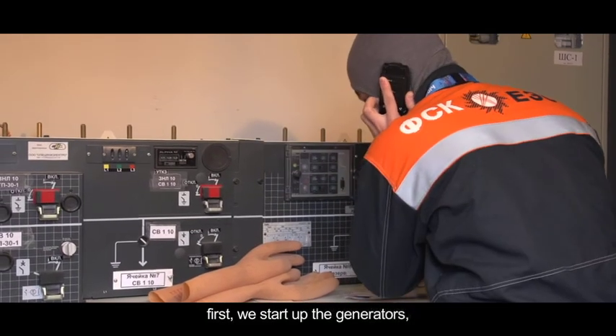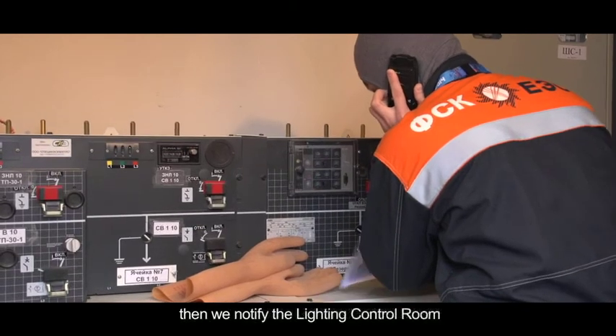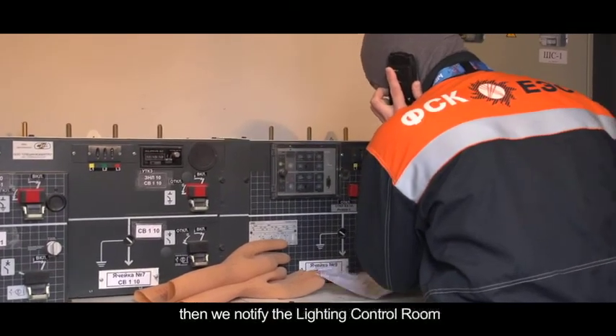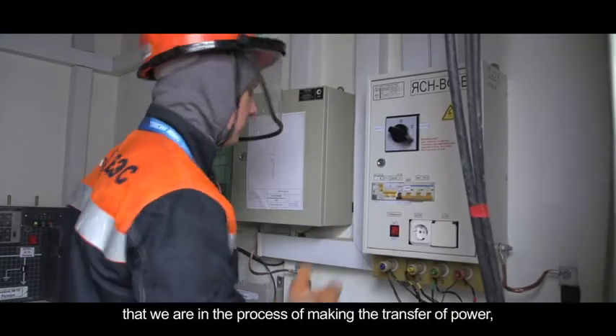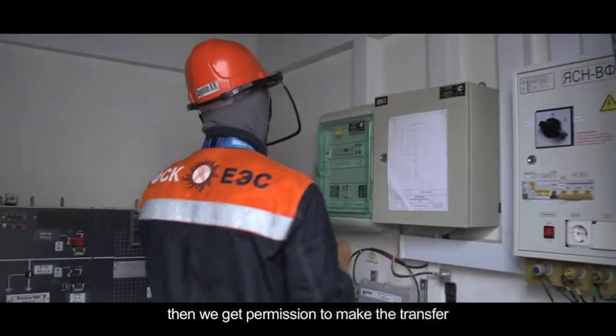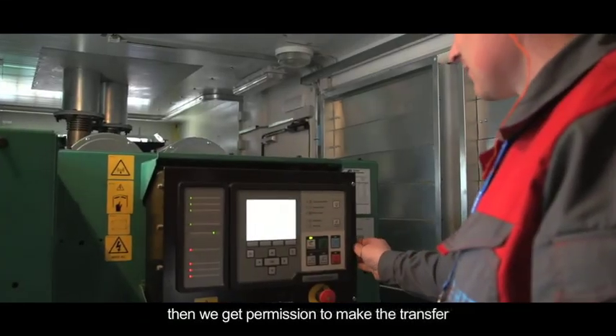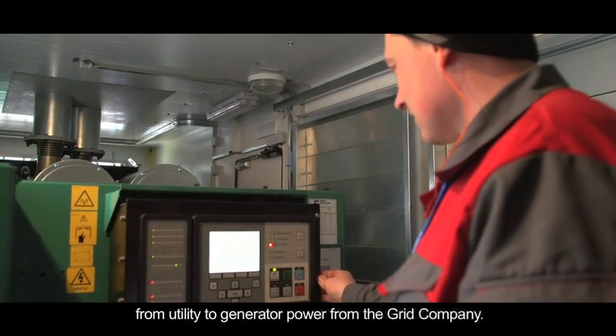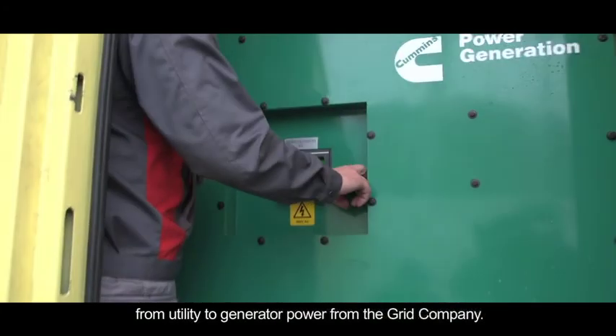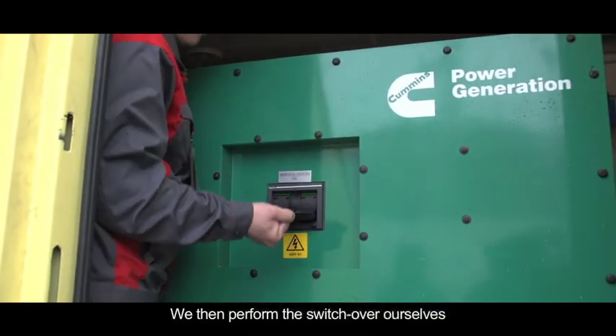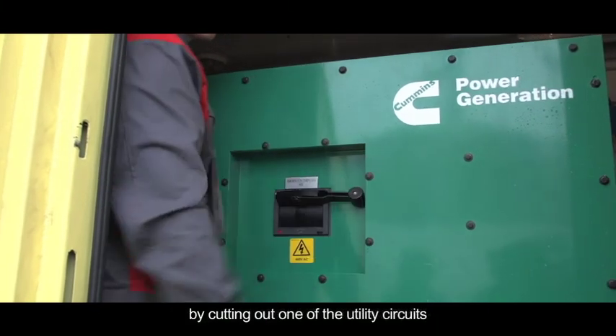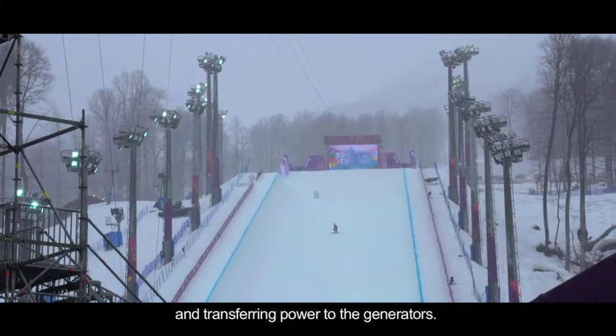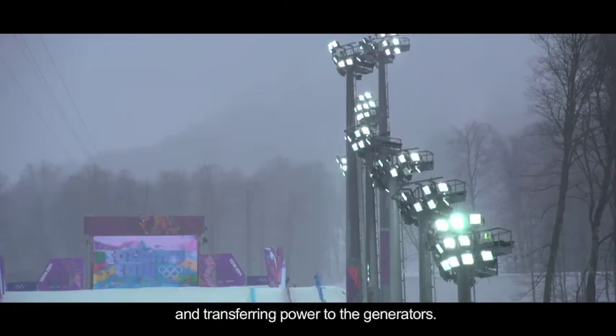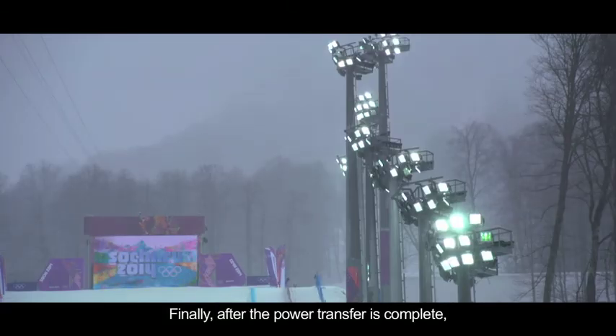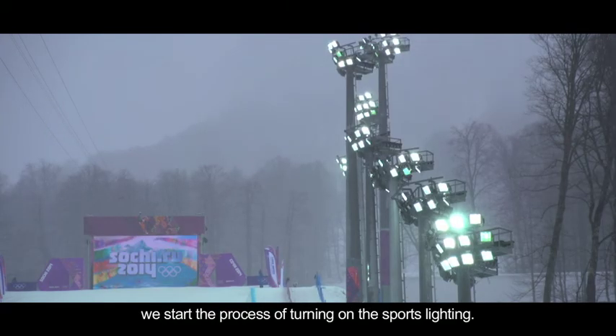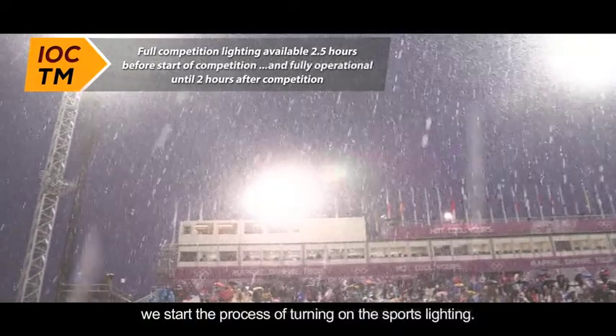First, we start up the generators. Then, we notify the lighting control room that we are in the process of making the transfer of power. Then, we get permission to make the transfer from utility to generator power from the grid company. We then perform the switchover ourselves by cutting out one of the utility circuits and transferring power to the generators. Finally, after the power transfer is complete, we start the process of turning on the sports lighting.